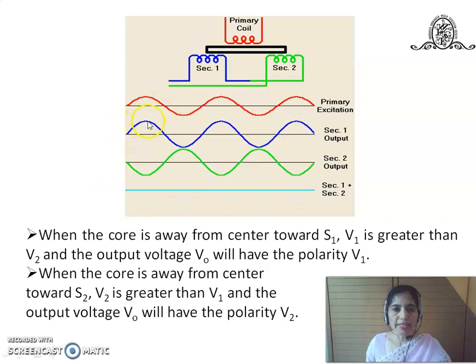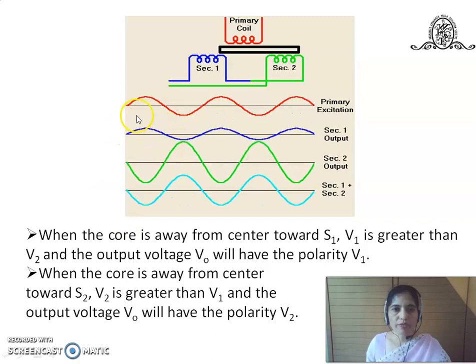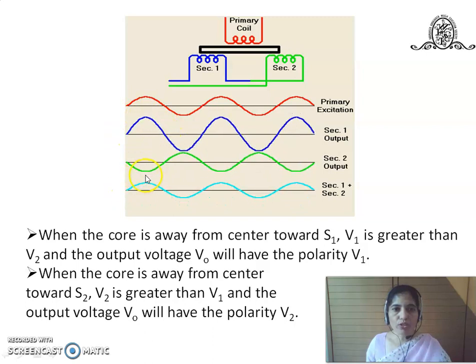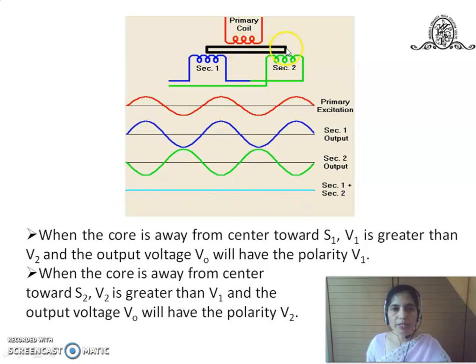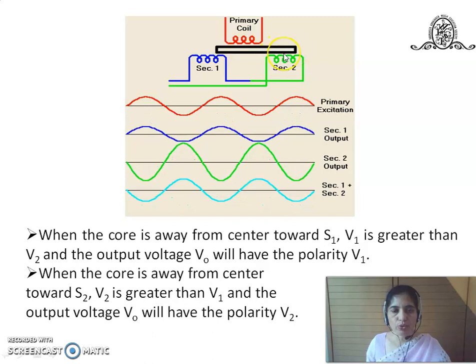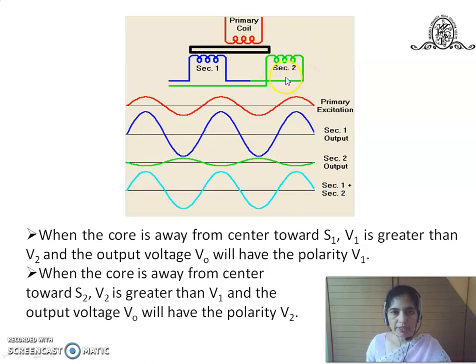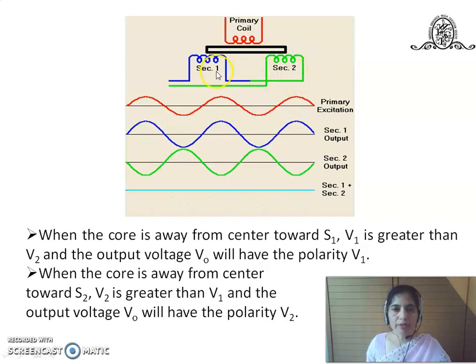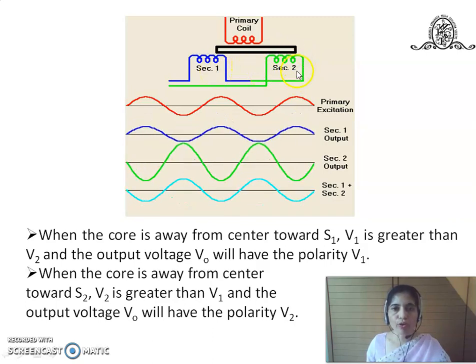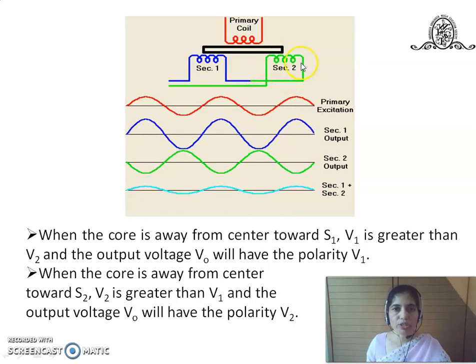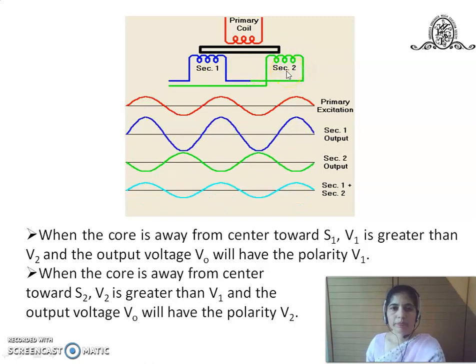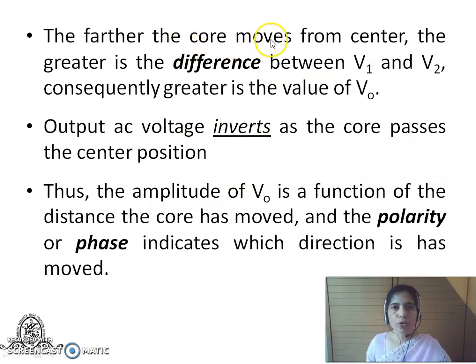So you will find that if the voltage in the secondary is rising in the positive direction, the output voltage will also rise in the positive direction. Now, if the movable core moves towards secondary 2, that is S2, then the voltage induced in S2 will be greater. Therefore, V2 will be greater than V1, and the output voltage will follow the polarity of voltage V2. Thus, the farther the core moves from the center, the greater is the difference between V1 and V2, and consequently the greater is the value of the output voltage V0.